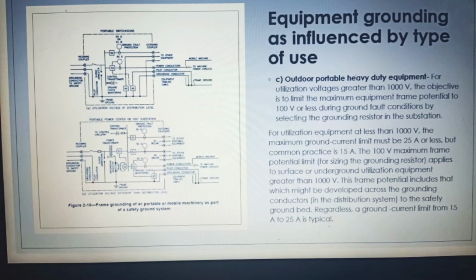For utilization voltage greater than 1000 volt, the objective is to limit the maximum equipment frame potential to 100 volt or less during the ground fault condition by selecting the grounding resistor in the substation. This picture relates to an application where a portable power center is connected to distribution, implying that utilization equipment is operating at lower voltage than distribution. The power transformer configuration is selected to separate ground fault condition in the utilization portion from distribution. The pickup of all the ground fault relay is typically set at 40% of the established ground current limit.